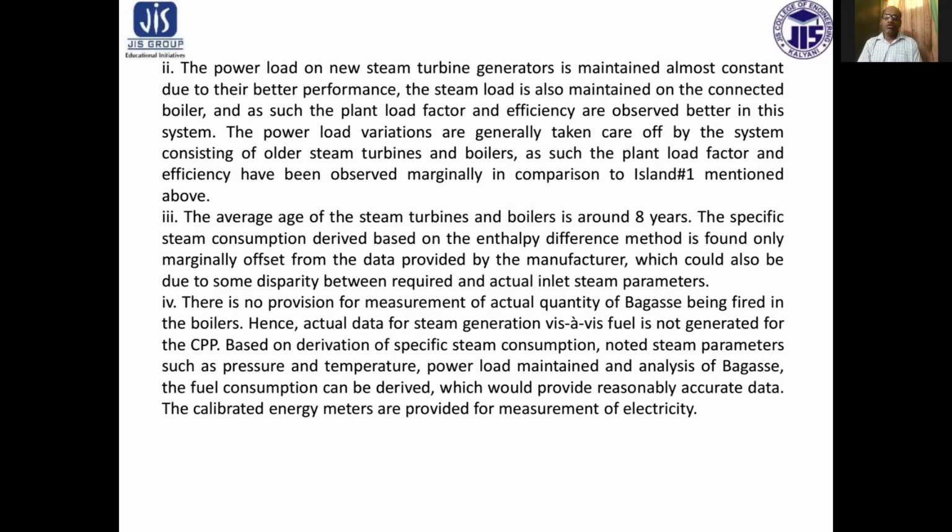The power load on the new steam turbine generator is maintained almost constant due to its better performance. The steam load is also maintained on the connected boiler, and as such the plant load factor and efficiency are observed to be better in this system. The power load variations are generally taken care of by the system consisting of the older steam turbine and boiler.